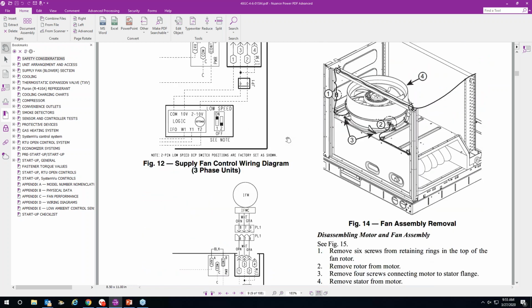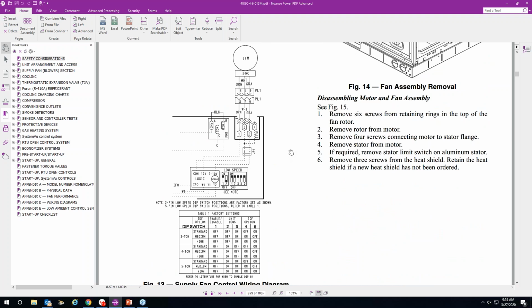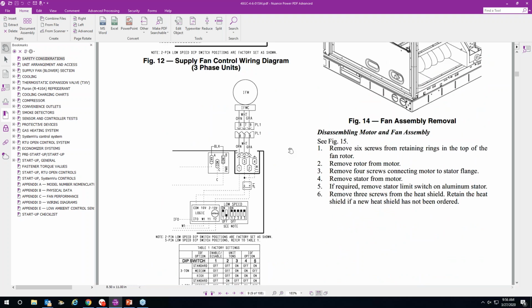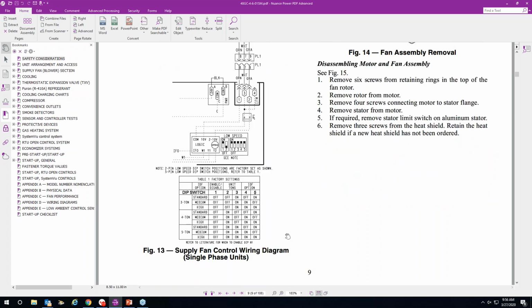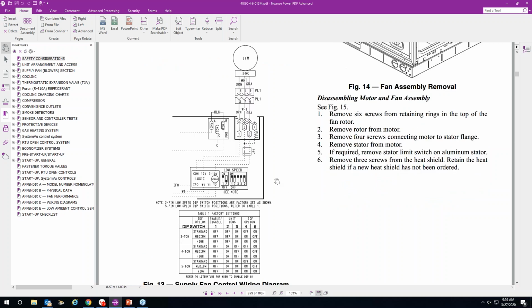Go down here to the single phase. The nice thing about doing this class live is we go out into the lab and we actually look at these points and throw a meter on it. But I'll try to explain it the best I can this way. This is just a single phase version of the same thing. The orange is still going to be your 10 volts DC coming from the motor to the board, and gray is going to be your reference signal back to the controller.